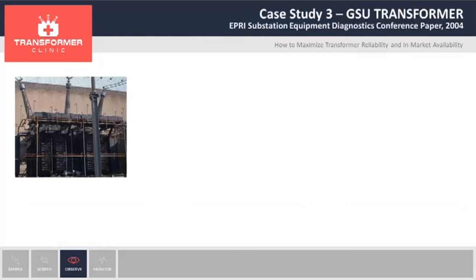The next case is for a GSU transformer — a shell form that has been in service for 20 years. The transformer was in service after that time and suddenly started gassing. The main gas was ethylene, and the gassing rate was up to 60 parts per million per day. With that gassing rate, they knew they had a problem. The question for them was: can I open the transformer on-site, or do I need to ship it to the manufacturer? A transformer of this size — just the shipping cost — we are talking about $300,000 to $400,000 just for shipping. So they decided to call us to do an acoustic test.